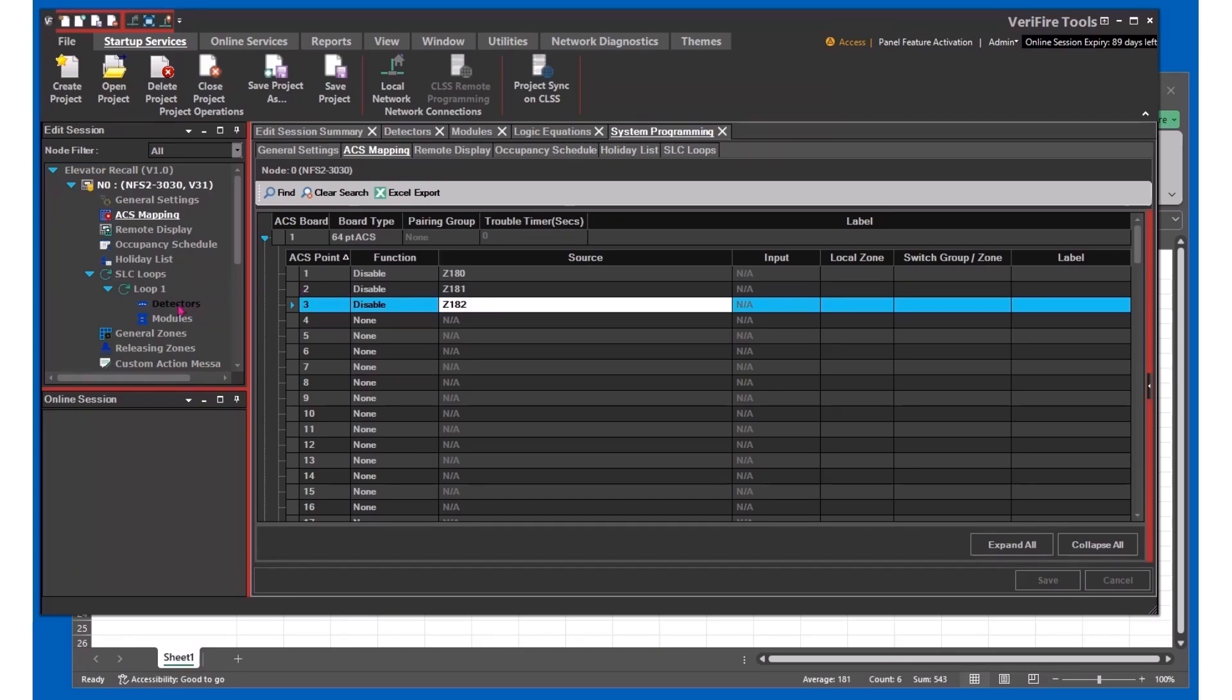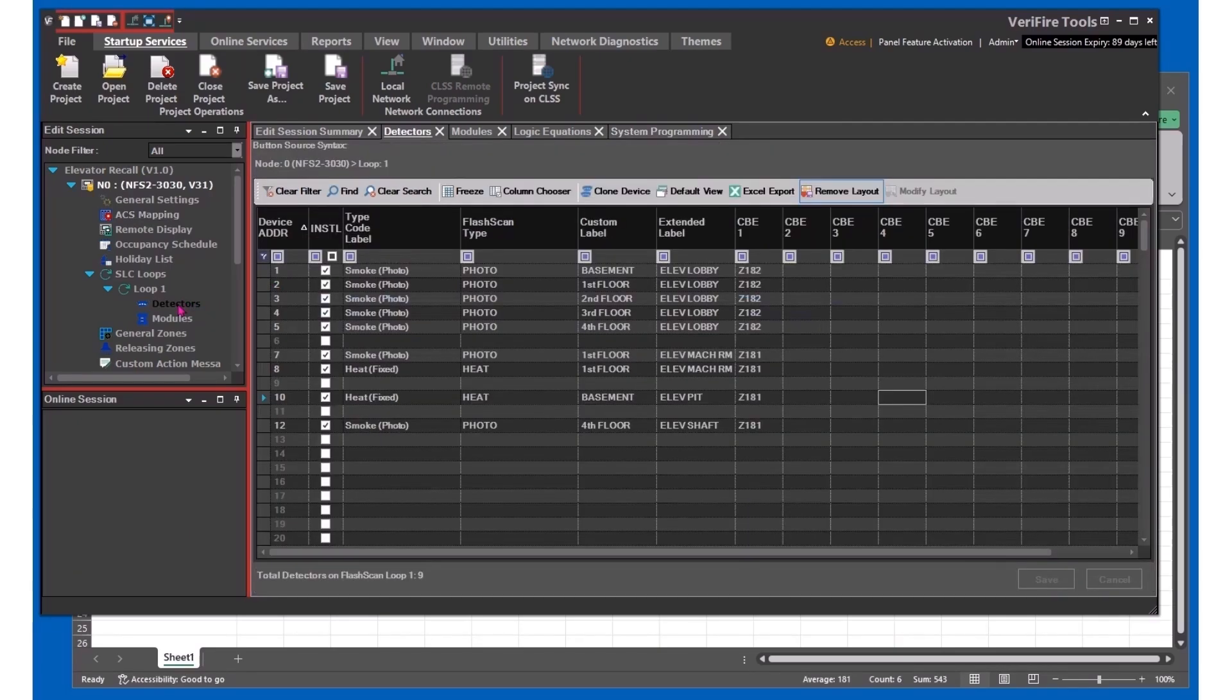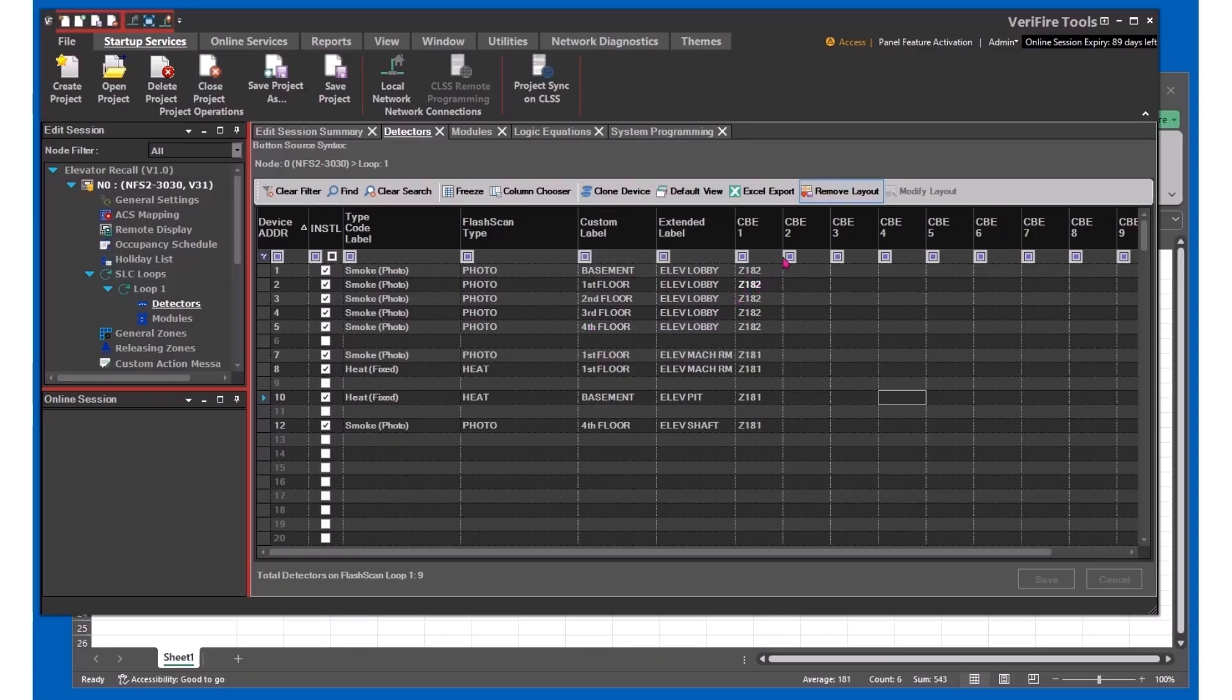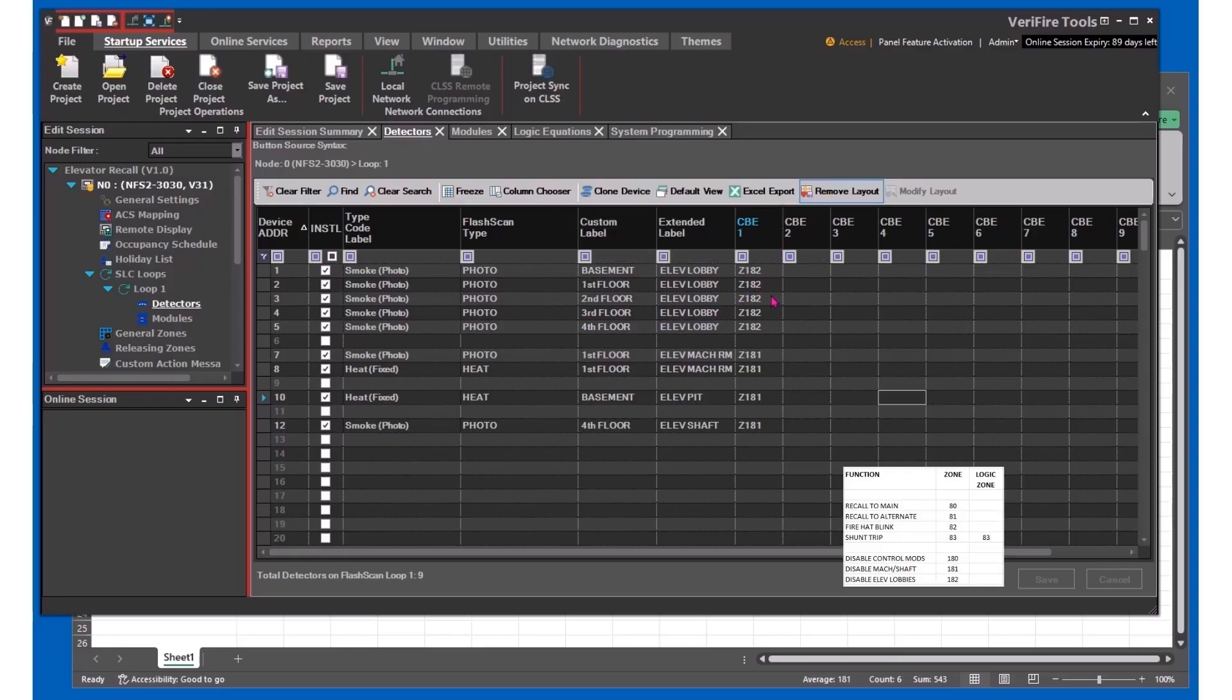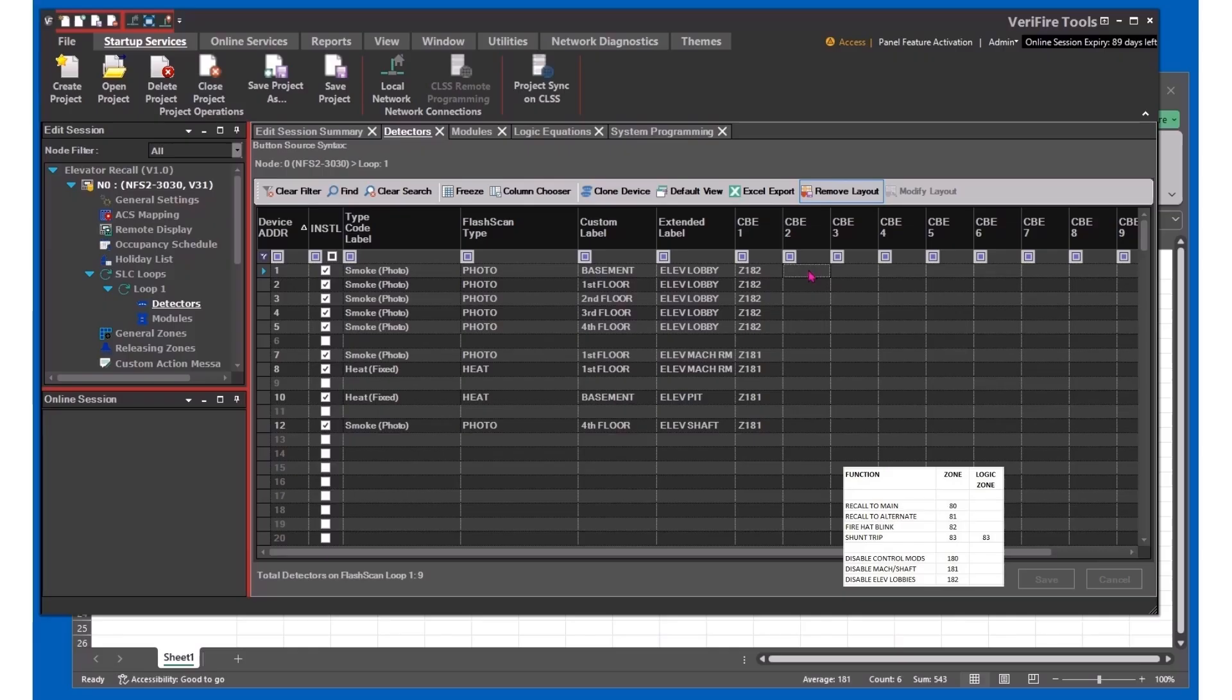Now we'll go to our input devices or detectors, and we've already programmed a few things here. In CBE1 are those zones that we're going to be using for bypass. Now we've got to program the specific output for each detector based on which zone and therefore control module we want to activate.